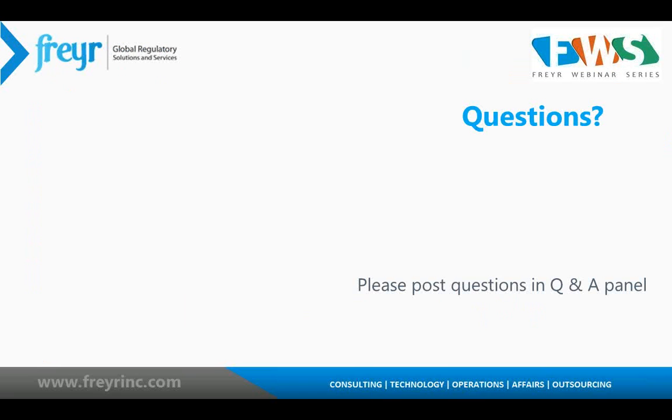Yes, sorry, I was on mute there for a second. So, how will Freyr assist in activating the GUDID account? Really, we start off with Freyr sending a request to the FDA on behalf of the labeler for a GUDID test account. That's where you start. So they can validate that each labeler is compliant with submission.